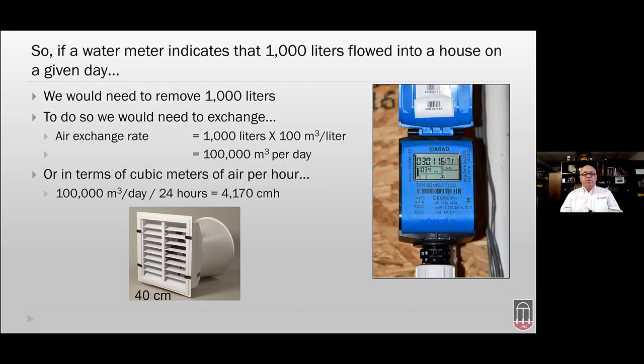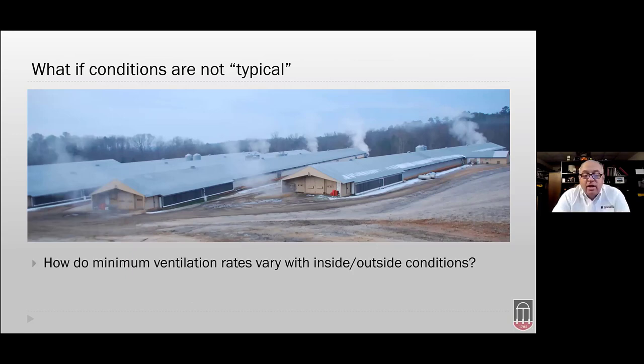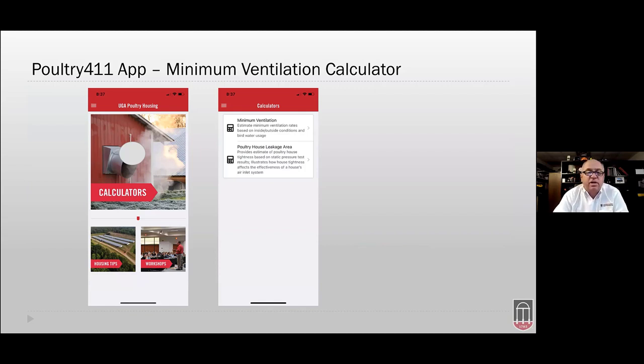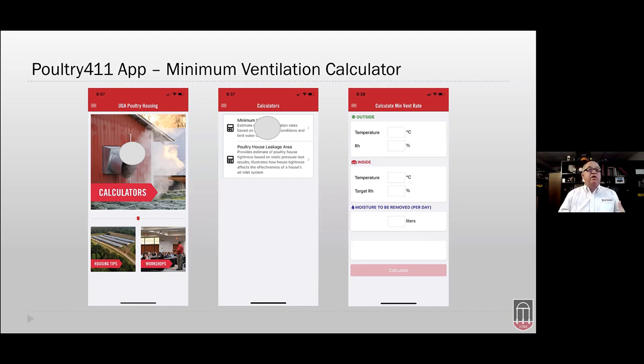What if conditions are not typical? How do minimum ventilation rates vary with changing inside and outside conditions? We developed an app for that — it's called Poultry 411, available for Android and iPhone free of charge. You open the app, click on Calculators, then click on Minimum Ventilation. The calculator asks for outside temperature and humidity, inside temperature and target humidity, and the amount of moisture to remove per day — generally determined by your water meter. More water in means more ventilation needed.